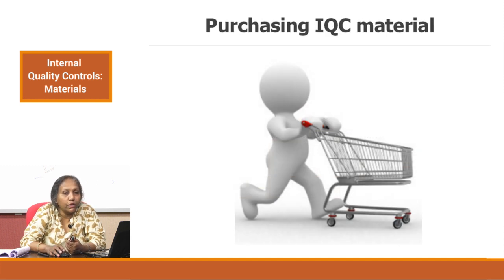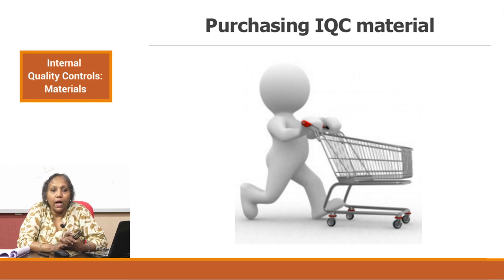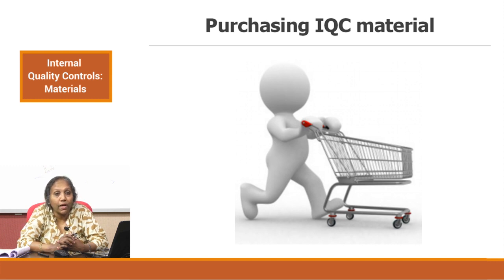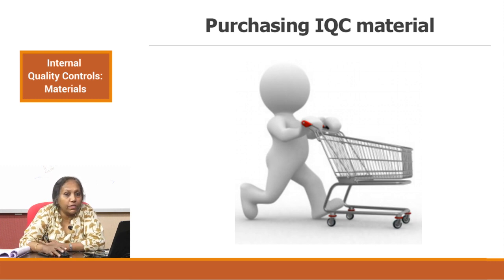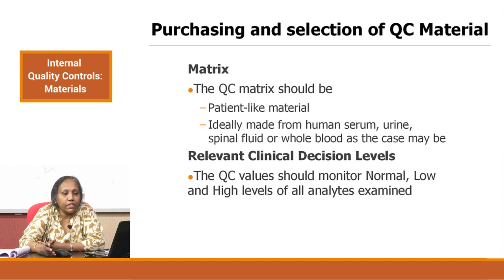One more thing about QC material is what to consider when purchasing it. While it is not entirely up to the laboratory to decide on which QCs to get, you do have a say and should have an understanding of good quality control materials. Please read through literature which gives you ideas about how to purchase quality control material. The first consideration is the matrix — the material in which all your analytes are suspended. The QC matrix should be patient-like material.